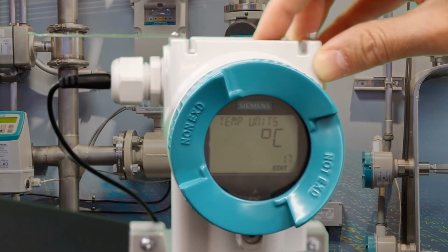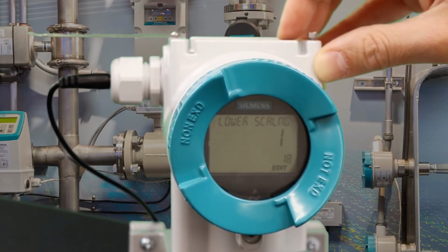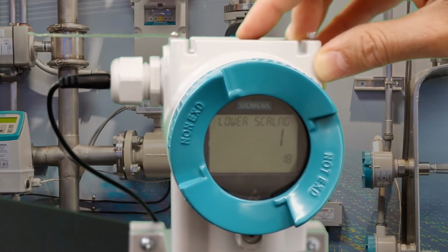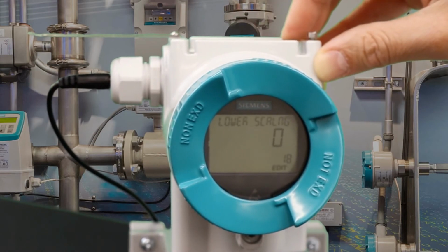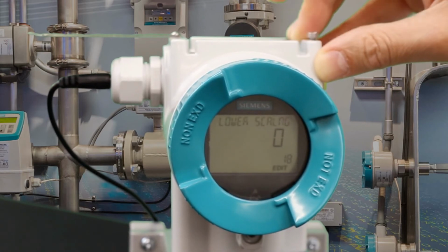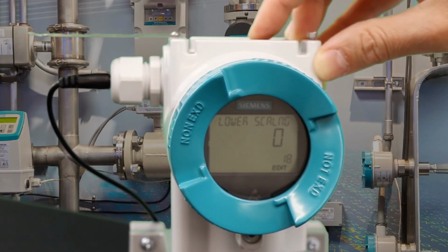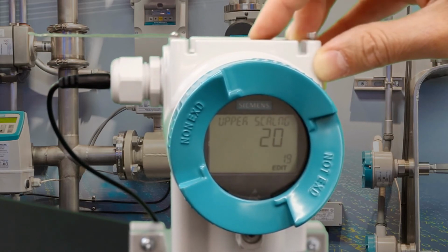And going to parameter number 18, this is your lower scale. All right, make sure this is going to show 0, because you remember the pressure transmitter is located at the bottom of the tank. We don't need to offset anything. All right, now it's 0. Lock it by clicking on the right arrow. Going down. All right, the upper display setting is at 20 feet, where we want it to be.